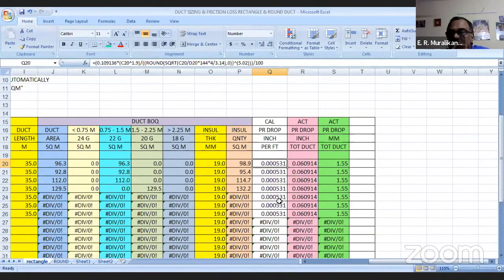All these indoor cassettes are not meant for high enthalpy sudden shocks. Suppose suddenly weather changes, the enthalpy goes high, and the cassette AC will not take that much load. So I never recommend this idea of putting a fresh air port in the cassette ACs. Next, please.